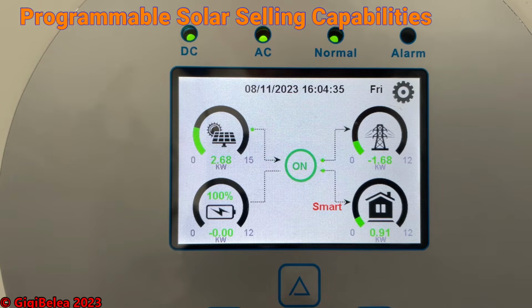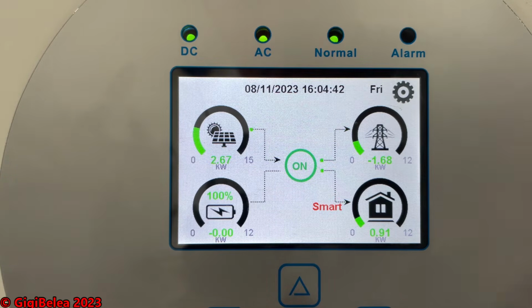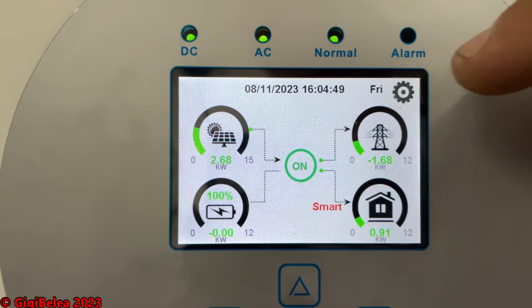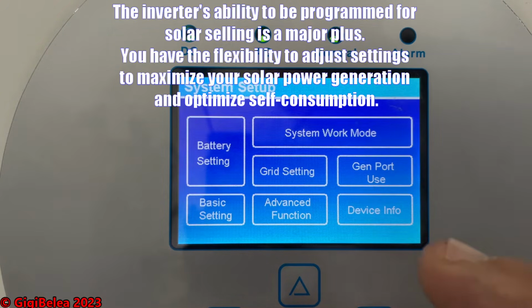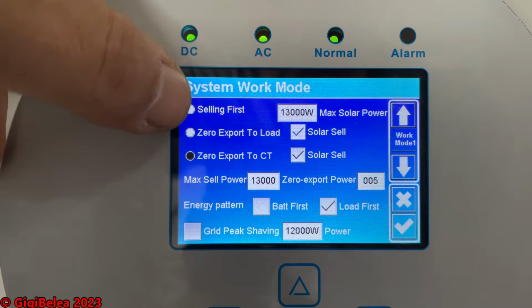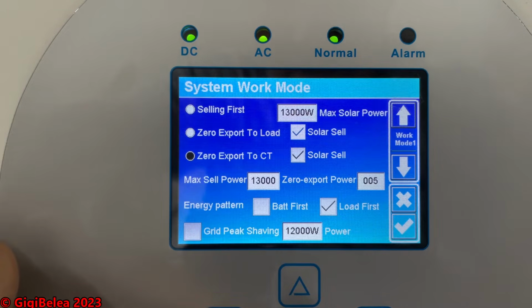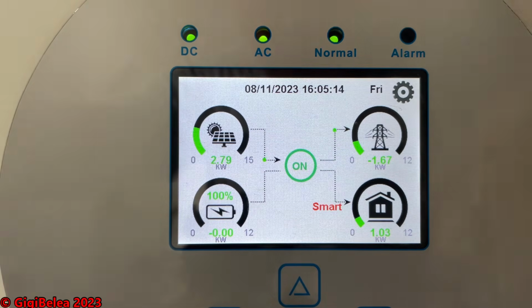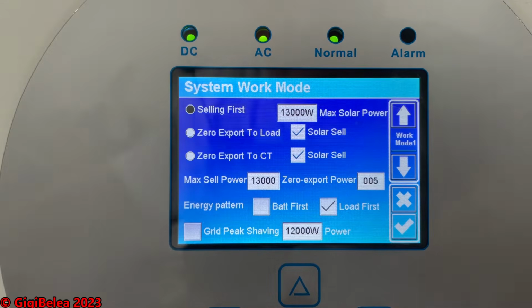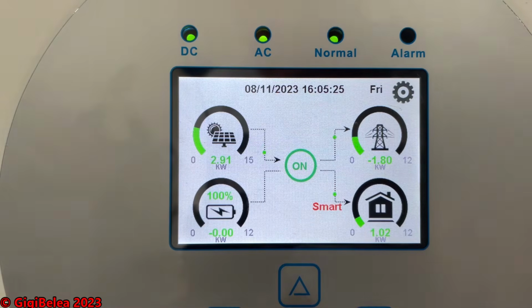The next good feature on this inverter is the programmable solar power selling capabilities and settings. You can choose to sell, not to sell, when and how. Let's go to the system work mode, where we have the primary system work mode screen. If I select selling first, it will sell all the energy it can get without capping it. Right now I'm producing 2.7, sending 1.6 to the grid. If I select selling first, accept, confirm, and go out, it will start selling all it can, and it will also draw from the batteries.